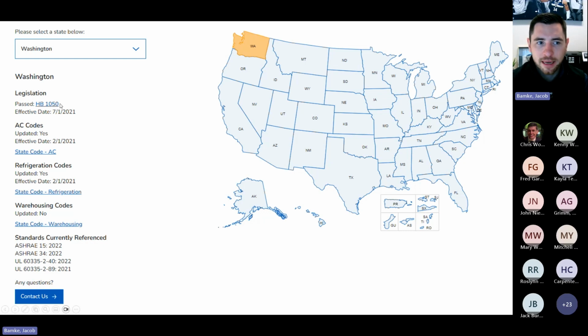This legislation basically means that you can install something. So nothing is preventing that state from installing A2L refrigerants. But if they don't have their codes updated, they don't give direction on how to install it or service it safely. So it's basically, go ahead, we're not going to stop you because we know manufacturers have to, but we're also not providing any direction on how to do it. So that's where it gets a little bit tricky, wanting to really make sure that we push all the states to start adopting all of these refrigerant codes.